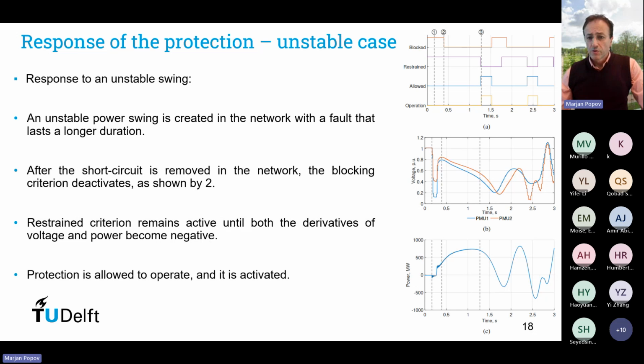In the second case, we used the same contingency. The fault lasts for a longer period of time so that the critical clearing angle is exceeded and unstable operation in the power system takes place, followed by power swinging. So in this case, we see that up to time instant three everything seems the same. However, the protection remains here unblocked until we see that the conditions for waiving the restraining are also fulfilled, and the restraint here drops to zero, which allows the protection to operate, right? So we see the blocking and restraining no longer exist. Protection may operate, and the conditions for the protection to operate are fulfilled because the algorithm detects that this is an unstable power swing.